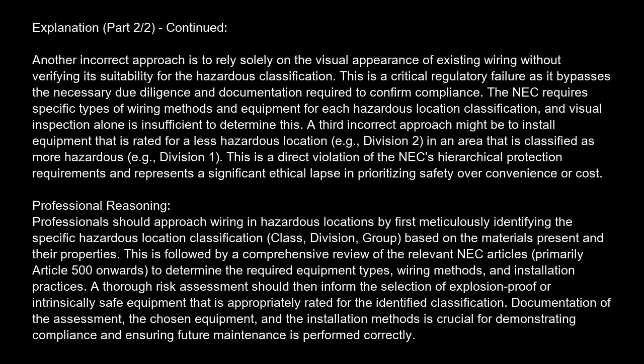Another incorrect approach is to rely solely on the visual appearance of existing wiring, without verifying its suitability for the hazardous classification. This is a critical regulatory failure, as it bypasses the necessary due diligence and documentation required to confirm compliance. The NEC requires specific types of wiring methods and equipment for each hazardous location classification, and visual inspection alone is insufficient to determine this.